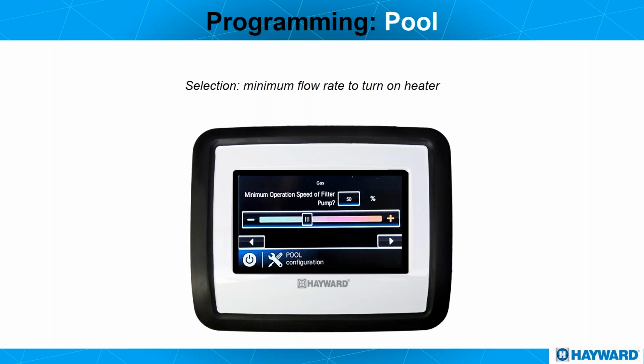Minimum speed, what does this mean? Well, maybe the flow switch will not close when the speed is very low, like for example 20%. So maybe we want to bring it up. Whenever the heater turns on, the speed will go up so we can have enough flow for the heater. And when the heater is off, it will go back to its regular programming.